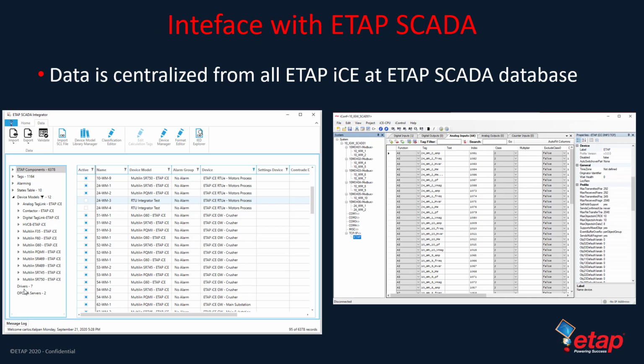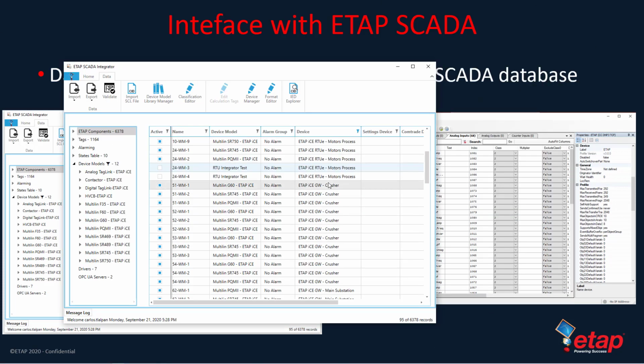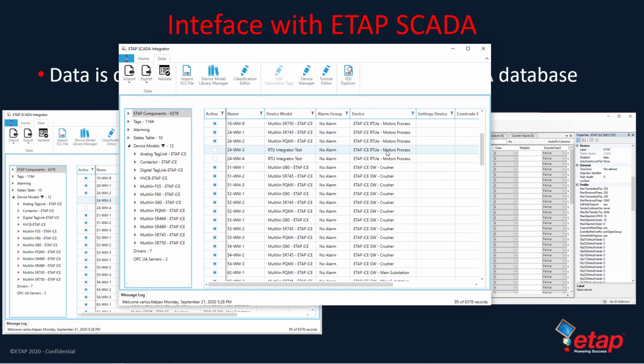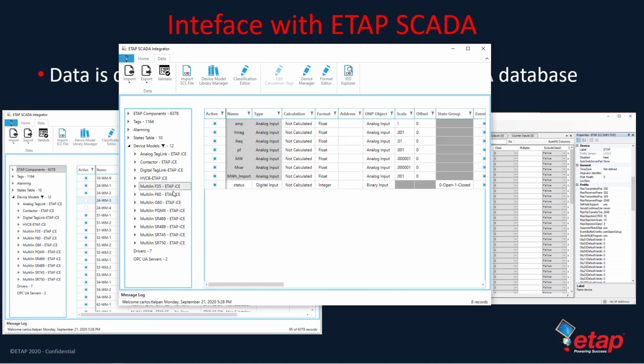Now the interface of a single device or multiple devices directly into my ETAP SCADA server is going to be via my ETAP SCADA integrator database. On my ETAP SCADA integrator database, this will allow me to monitor multiple ETAP iCE RTU or iCE Gateway devices across my network, and also monitor the state of all the measurements that I'm collecting. So in this case, when I'm working on my ETAP project, all I need to do is just create my single device, defining here what are going to be the measurements that I'm collecting from each one of my ETAP iCE devices.